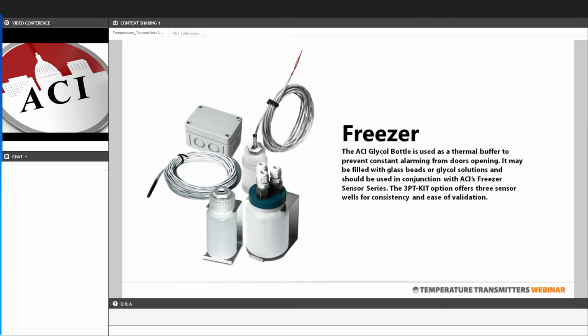Our freezer sensors come with a glycol bottle kit that acts as a thermal buffer to prevent your control system from going into alarm upon a shock of warm air from a freezer door or refrigerator door being opened. So if the door opens and this sensor without the glycol bottle were to get hit with a rush of 70-degree air, that could put the system into alarm.